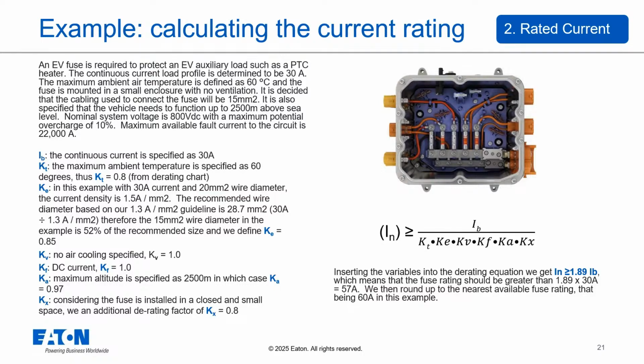Since there's no air cooling specified, K sub V is 1.0. It's DC current, so K sub F is 1. For the 2,500 meter altitude, K sub A is 0.97, and because it's a closed small space, we apply an additional K sub X of 0.8.